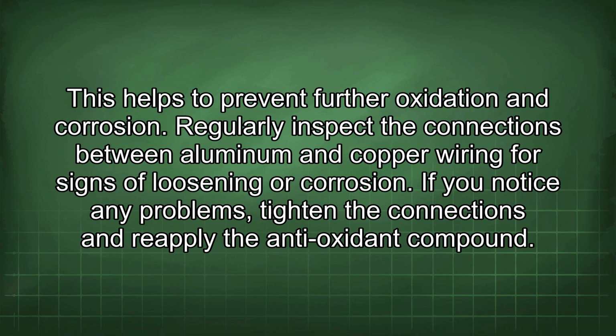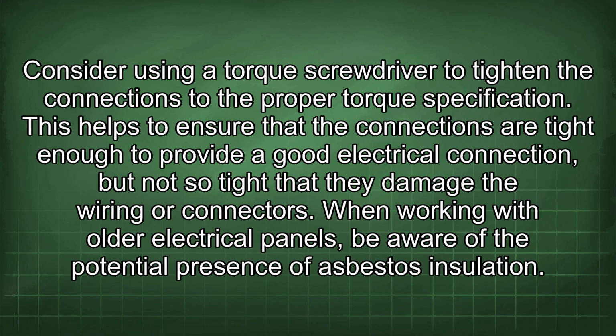Regularly inspect the connections between aluminum and copper wiring for signs of loosening or corrosion. If you notice any problems, tighten the connections and reapply the antioxidant compound. Consider using a torque screwdriver to tighten the connections to the proper torque specification. This helps to ensure that the connections are tight enough to provide a good electrical connection, but not so tight that they damage the wiring or connectors.